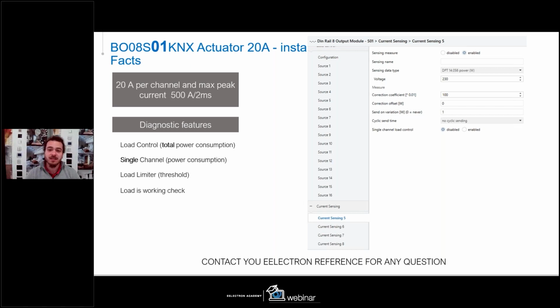Another very important function is the opportunity to understand if the load is present or not. This is because if I send the on command to the actuator and the actuator closes the relay, I estimate a consumption from the load that I connected. If the consumption remains zero or is less than the nominal consumption that I put in the ETS, it means that something is broken or is not working properly in the output. So this enables you a lot of functions, also for diagnostics, as you can see from this slide. And I think that will be a good product for your project and your solution.